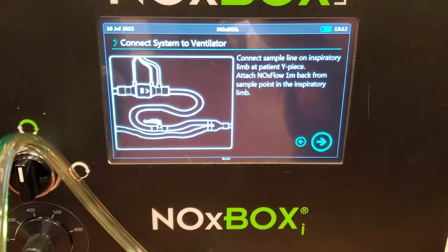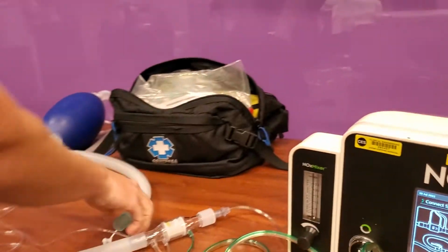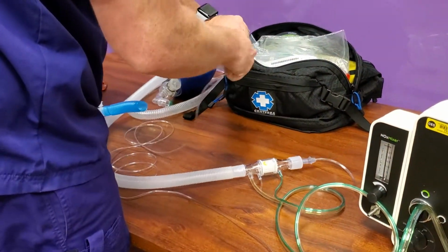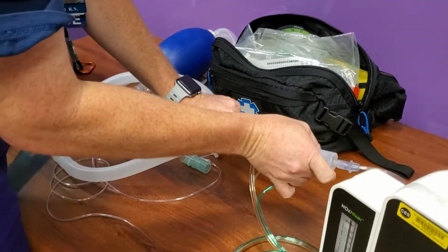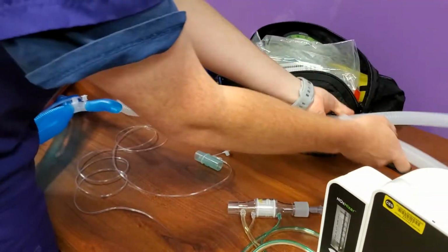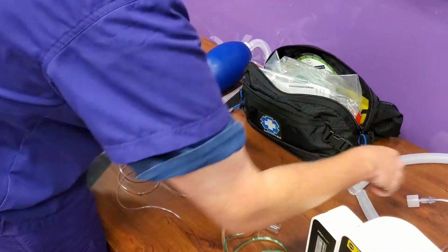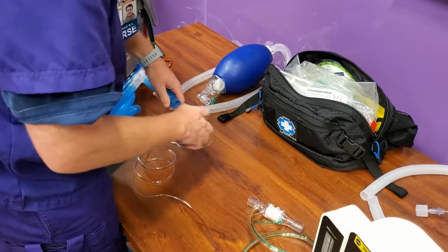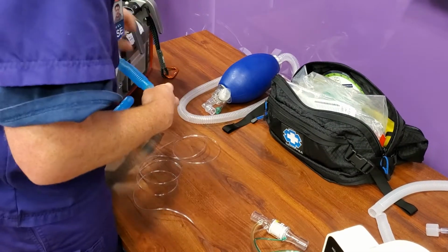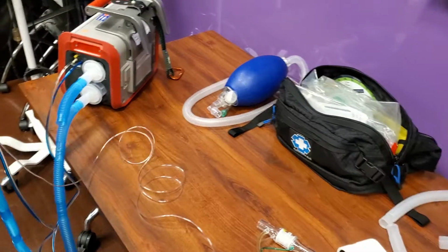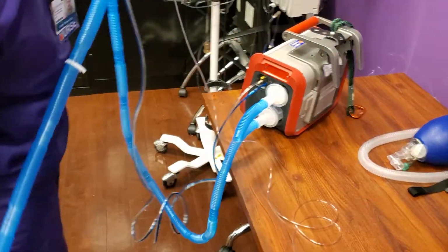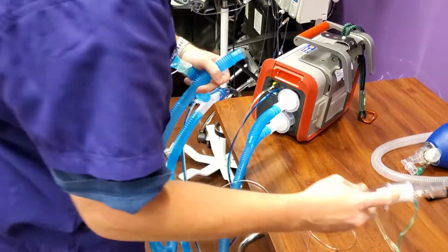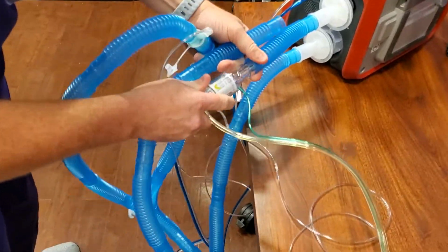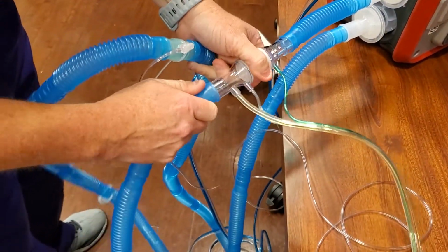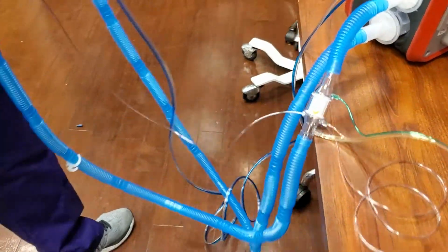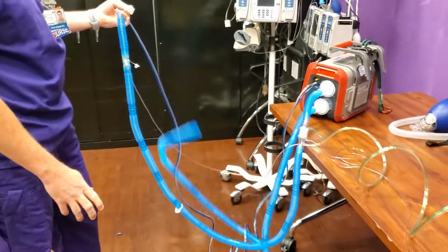So we can remove our test tubing here. Remove that piece there. Remove that. This piece also can be saved, going into our piece there for our next patient setup. But obviously we have our monitoring line here, which is going to connect just on there and just on there. And then the injector module itself, with the arrow making sure it's facing away from the ventilator, we're going to come just on here like this and in there like that. And that is ready as far as full setup. Now you can essentially hook the patient up to it right away.